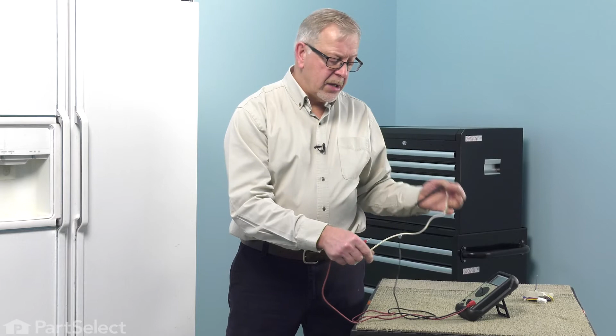The properties of a thermistor are that they have a specific resistance measured in ohms that is related directly to the temperature that the sensor is sitting in. So using a multimeter, we could measure that resistance for each temp sensor that may be located in your refrigerator, and you will also need the information from the manufacturer to tell you what resistance you would expect to see versus the temperature that that sensor is at that present time. To determine whether your temp sensor is accurate or not, you will need to contact the manufacturer to get the specifications for that particular sensor.